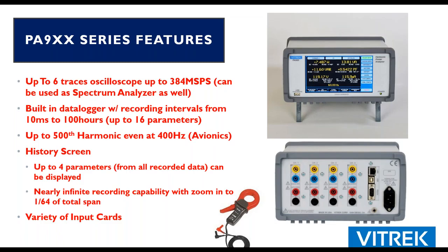The unit is also capable of measuring up to the 500th harmonic, even at 400 hertz, which is our avionics frequency. We have a history screen, which is really that long-term recording capability that I mentioned when you're doing, for example, maybe a power quality study for a week or 2 weeks or something along those lines. Our history screen allows you to look at up to 4 parameters from all of our recorded data. So any 1 to 4 can be displayed at a period of time. And there's nearly infinite recording capability with PA900s, with zoom capability up to 1/64th of the total span.